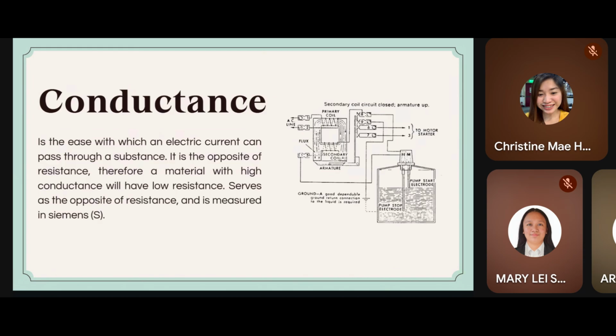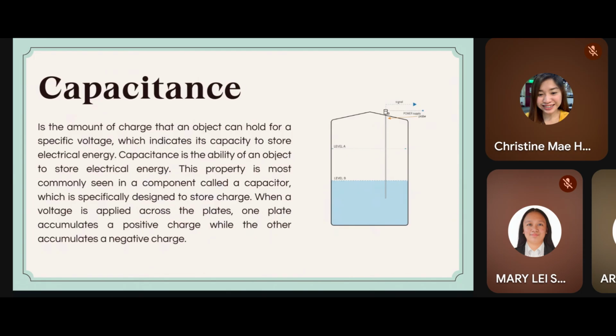Next slide, please. And of course, capacitance level measurement. So the main principle of this method is that the material to be measured acts as a dielectric between two capacitor plates. As the level changes, the capacitance value changes, which is measured electronically. It is best for both liquids and solids, and can detect granular or powdery materials. As for its application, it is continuous level measurement and even in non-conductive materials.